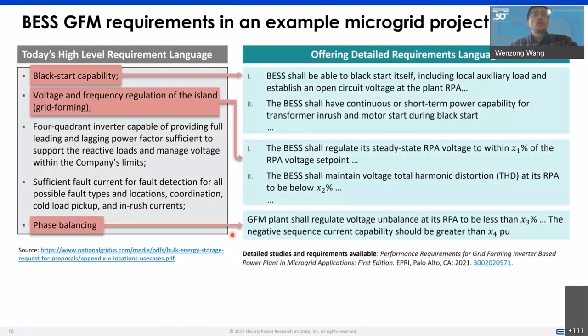If you look at a typical grid forming requirement in an example RFP, which is taken from a microgrid example in the United States, as you can see on the left-hand side, it's very high level. It requires black start capability, voltage and frequency regulation, phase balancing, but there's no detail about what the inverter should do or behave like in order to achieve those. So what we're trying to do here is dig into those areas and look at what specifically can be required of the grid forming inverter in terms of its performance.